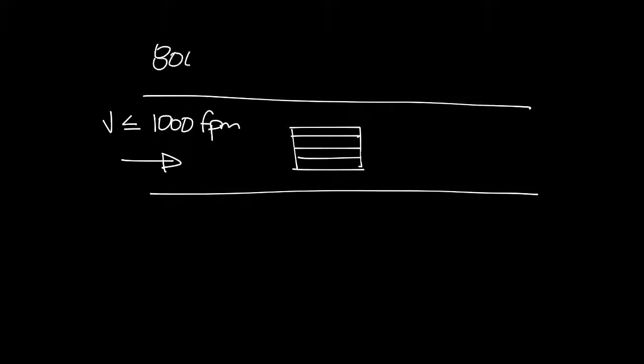So let's move on to this week. This week's topic covers 2 rules of thumb for spiral-mounted grilles. You often see grilles mounted directly to spiral duct, so it kind of looks like this. There are 2 rules of thumb to remember for this application. First of all, your velocity should be less than 1,000 feet per minute, and really 800 feet per minute is even better. So that's the first rule of thumb.